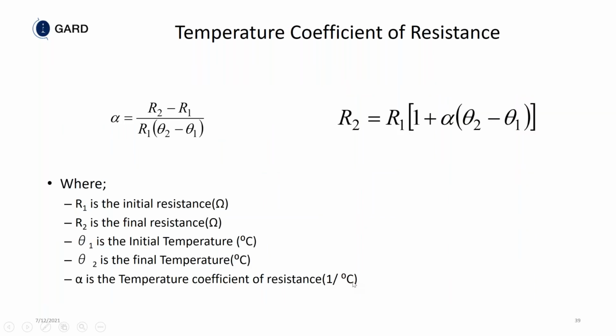Now, why is this important? It is important because we mentioned earlier the temperature coefficient of resistance, and the temperature coefficient of resistance is alpha. All manufacturers, or all consultants, understand that the lowest possible value of alpha determines the final resistance of your resistor. It's going to be a multiple of your initial resistance at ambient, and that alpha multiplied by the temperature rise, which we've already determined to be 750 or 760 degrees, depending on whether we're in Canada or using IEEE, is a multiple of the initial resistance. So when we specify that the temperature coefficient of resistance shall be as low as possible, what does that mean?